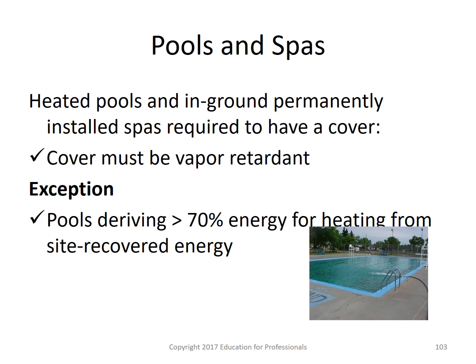And moving pretty much in the same format as the residential section that we presented before, we move into pools and spas, which for commercial buildings we find especially in hotels and any type of maybe executive office buildings. It's not 100% common, but it does occur. And again, this is exactly the same as for the residential requirements, and again, the cover must be vapor retardant, and you have one exception if you're using site recovered energy.